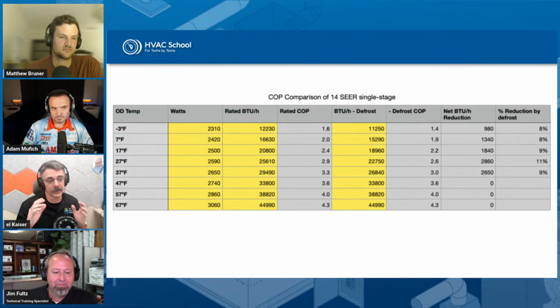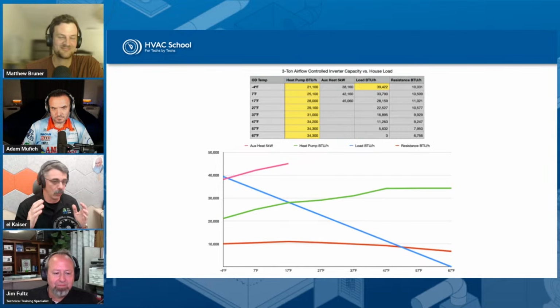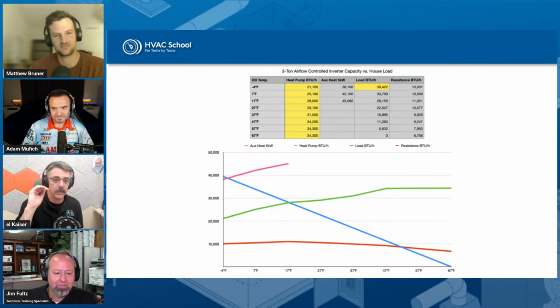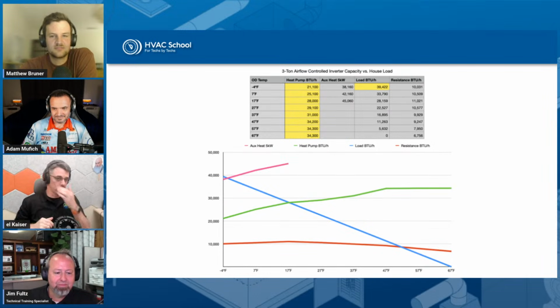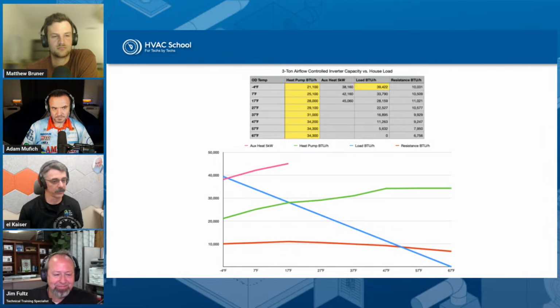And I'm going to show on the next slide what people are talking about, where they try to say to turn things off. Now, I took that 3-ton airflow controlled inverter heat pump. You'll see the green line is the heat pump performance curve. The blue line is my load slope on the house. So as it gets colder, load keeps increasing. And we're going to say on this one that the calculated load is somewhere around that -3 point. This actually worked out really beautifully when I calculated all this out, because this is an actual load slope that I used.